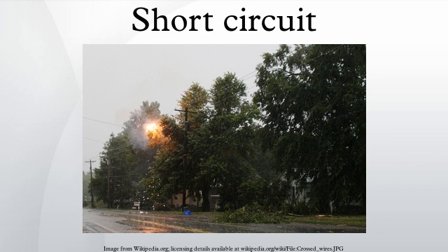Damage. Damage from short circuits can be reduced or prevented by employing fuses, circuit breakers, or other overload protection, which disconnect the power in reaction to excessive current. Overload protection must be chosen according to the current rating of the circuit. Circuits for large home appliances require protective devices set or rated for higher currents than lighting circuits. Wire gauges specified in building and electrical codes are chosen to ensure safe operation in conjunction with the overload protection. An overcurrent protection device must be rated to safely interrupt the maximum prospective short circuit current.